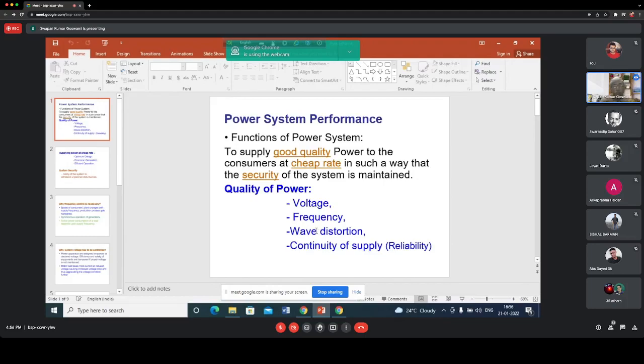Waveform distortion is not within our purview, particularly in this semester, so we shall avoid that also. What we shall discuss in this paper is basically regarding the voltage and frequency, how they may be kept within the acceptable limit. Voltage will vary, but how you can control the variation of voltage, limit the variation of voltage, compensate for the variation of voltage. And frequency also will vary, how the variation of frequency can be limited to a very small specified limit, how voltage can be controlled, how frequency can be controlled. These things will be discussed.